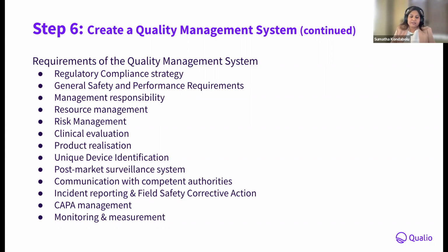I have seen that between the design and the production team, if there is a communication gap, and changes made in the design are not communicated, they end up having a non-conforming product. So make sure that this communication is right at the beginning, and also during, if you make any changes in the design. Verification of the UDI assignments made in accordance with the MDR requirements, that is, all relevant devices, and ensuring consistency and validity of information provided in accordance with the MDR.